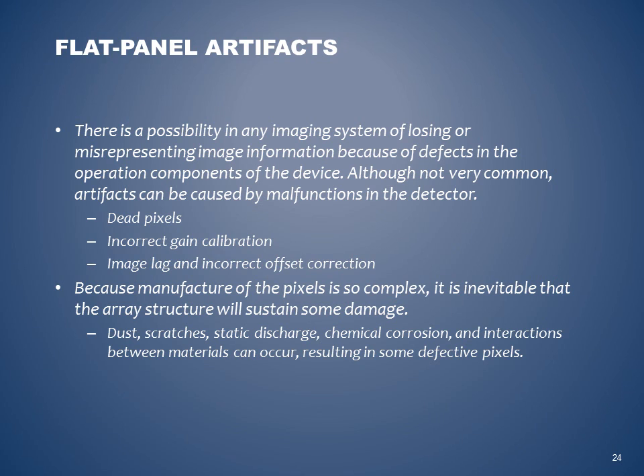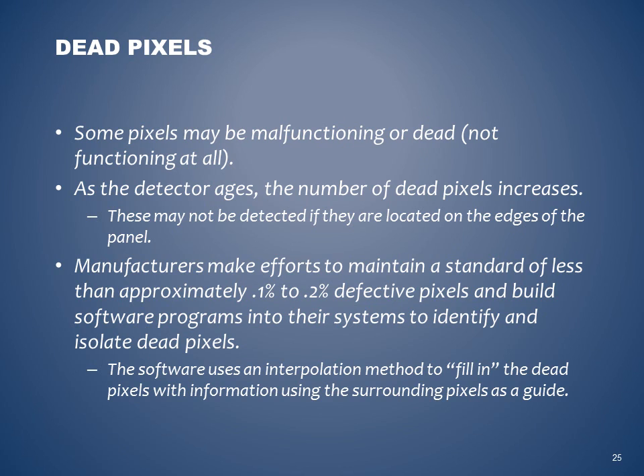Because manufacture of these pixels is so complex, it is inevitable that the array structure will sustain some damage. Dust, scratches, static discharge, chemical corrosion, and interactions between materials can occur, resulting in some defective pixels. Dead pixels. Some pixels may be malfunctioning or dead, not functioning at all. As the detector ages, the number of dead pixels increases. These may not be detected if they are located on the edges of the panel.